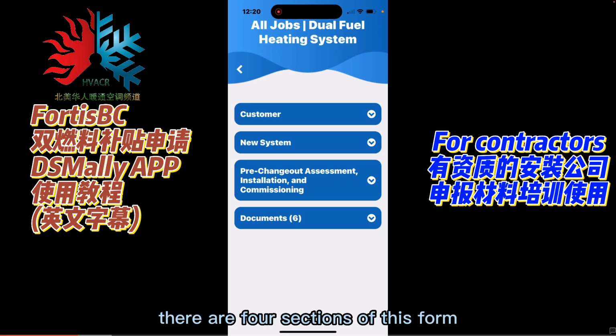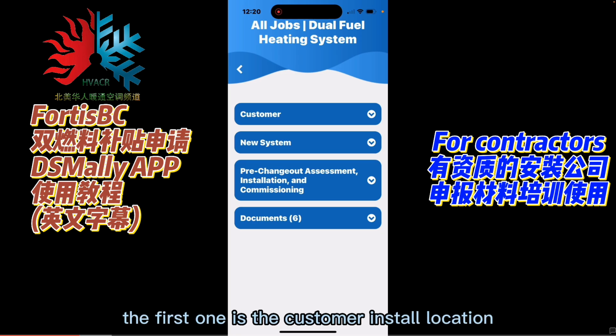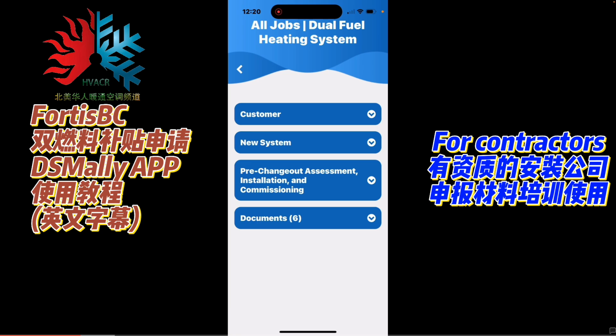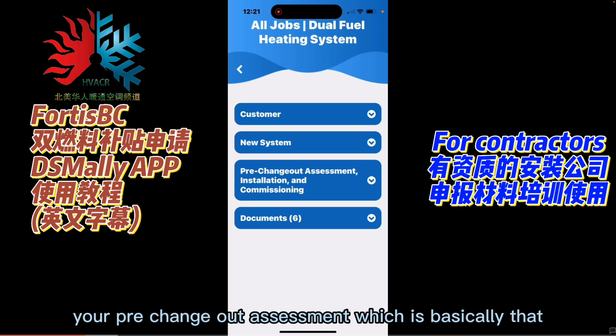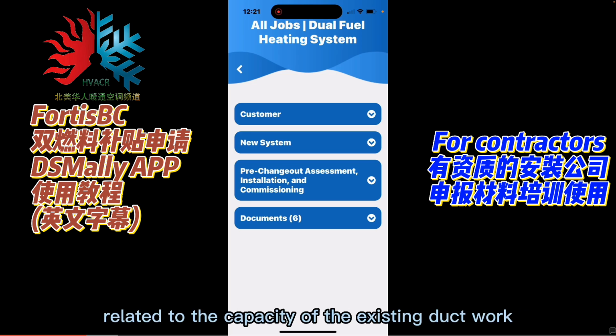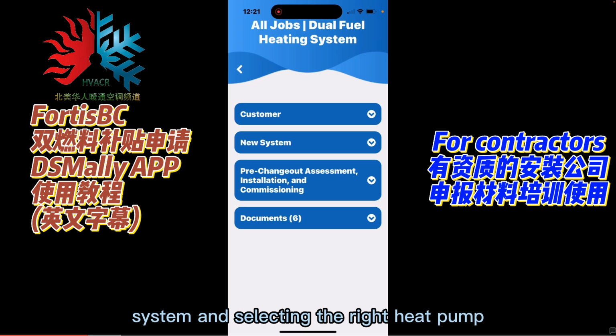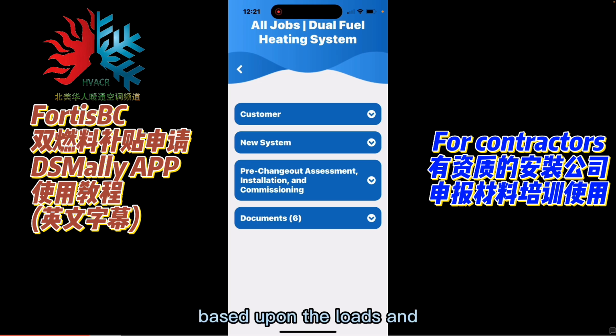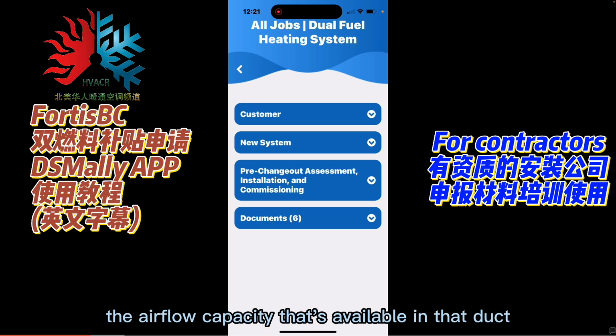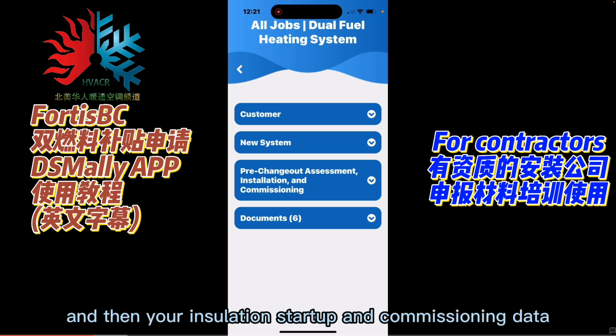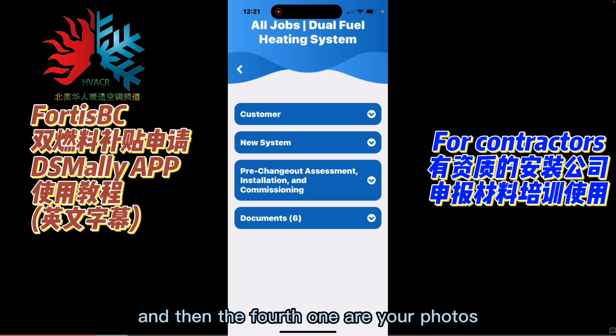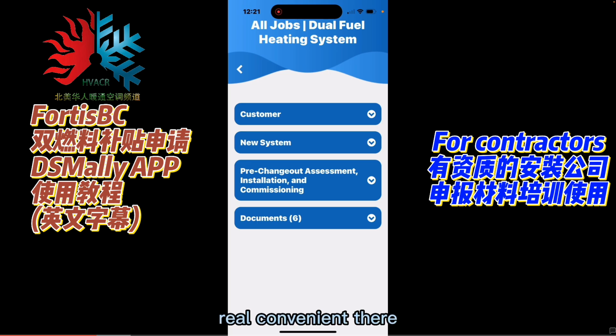There are 4 sections of this form. The first one is the customer and install location. The second one is the system that you sold and installed. The third one is your data, your pre-change out assessment, which is basically related to the capacity of the existing ductwork system and selecting the right heat pump based upon the loads and the airflow capacity that's available in that duct. And then your installation, startup, and commissioning data. And then the fourth one are your photos. Real convenient there. You can use the camera right here on the app, okay?